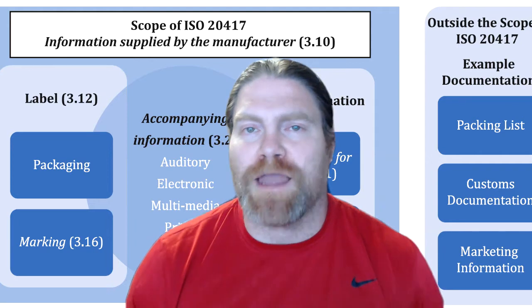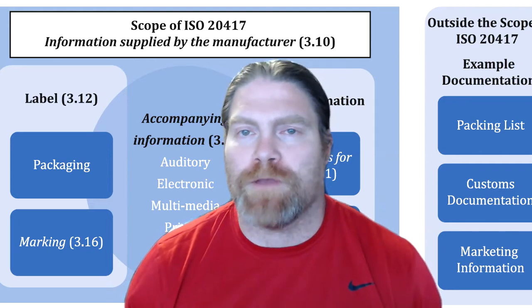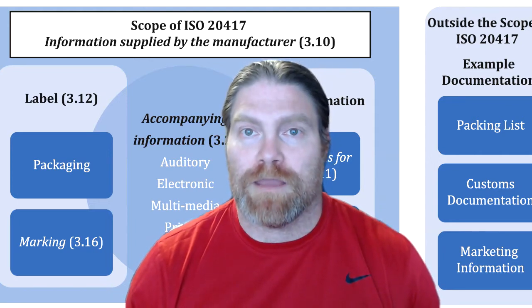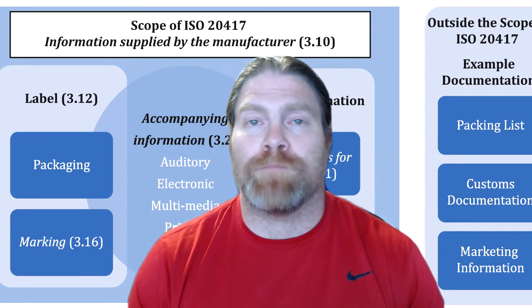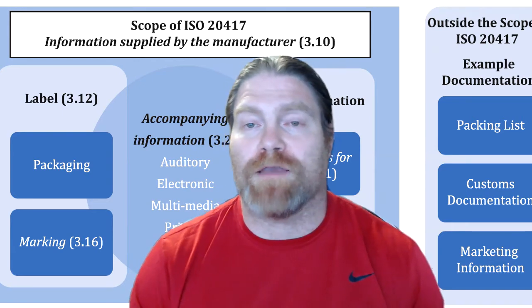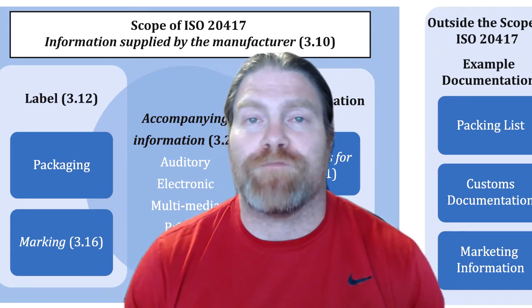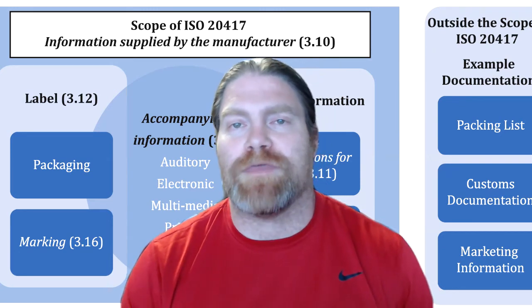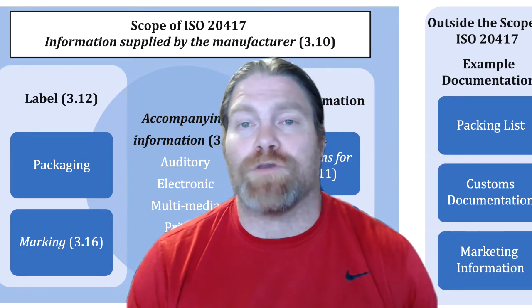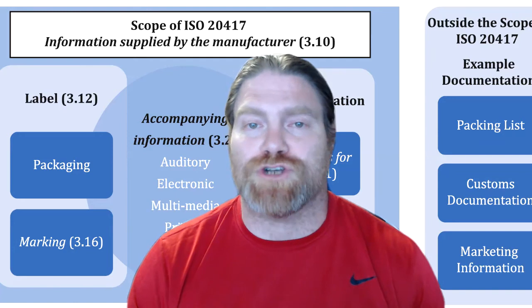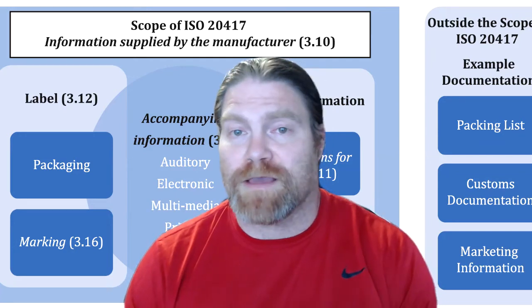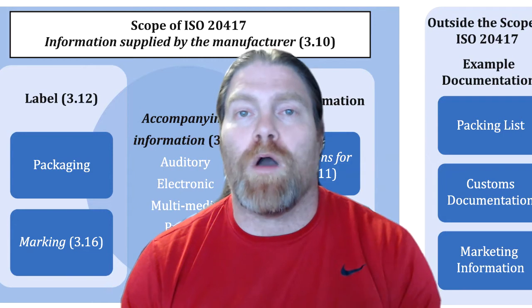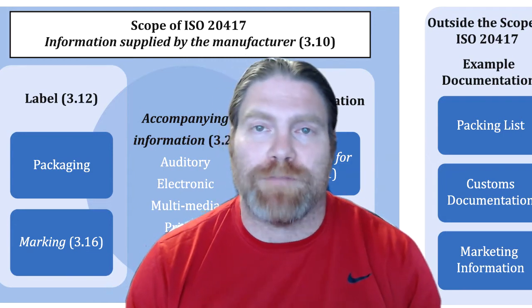First of all, there's not even a requirement for a labeling procedure in the MDR. In fact, there's not even a requirement for compliance with ISO 13485 or ISO 13485 certification. If you look in Article 10 of the MDR, that's where it requires that you have a procedure for different things, but not labeling. That's where it requires that you have a quality system, but not labeling.